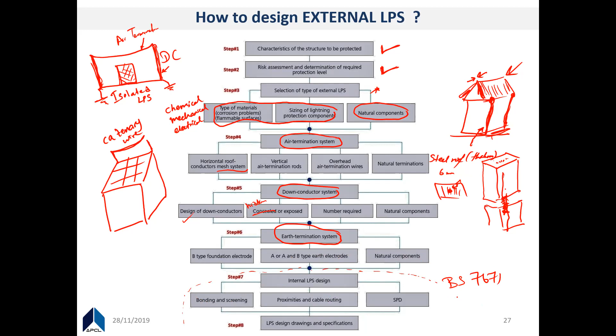So the number required will be checked with the design and natural components, like I mentioned. For earth termination, you can have different types of foundation to act as the electrode itself, or have additional electrodes along with these natural components. But you have to take care of the integrity of these natural components. I'll show you what these natural components are, and we'll cover internal LPS design later in the session as time permits, because it's actually a separate area of expertise we have to focus on. This is also given in the BS 7671 standard, which is now mandatory to be practiced correctly in Sri Lanka as per the Sri Lanka Electricity Act.